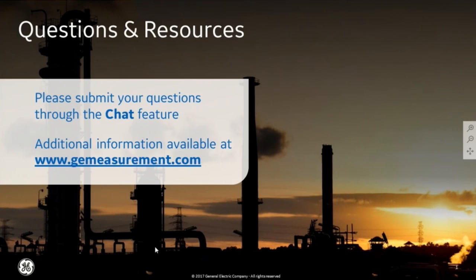Yep, it sure can. And that's just a function of having a standard of those standard materials, and it'll calibrate to it. And as I demonstrated, I use the IIW block because it's a very ubiquitous block. There are lots of those around the industry.